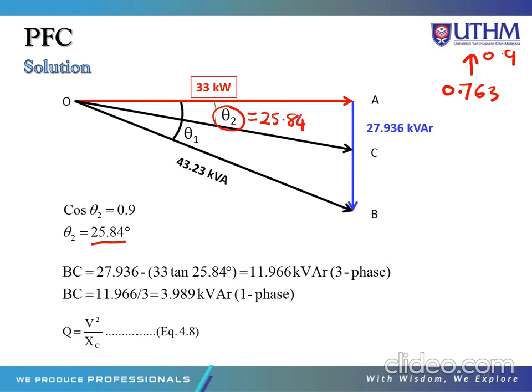So with this theta, we can calculate what is the AC. AC is the Q for the new system with improvement to 0.9 power factor. The kVAR that we have to supply to improve the power factor is represented as BC. This is the kVAR that will be installed to improve to AC. So we have to get the BC.